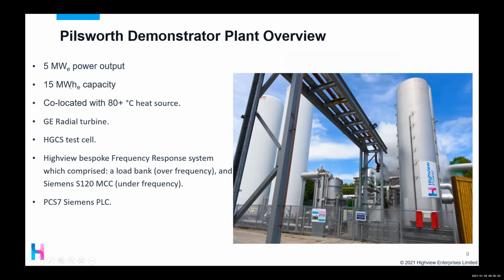It had a 15 megawatt hour electricity capacity. So at nominal power, we've got about 3 hours worth of storage. As I said before, we were co-located with approximately 80 degrees Celsius of heat. We used a GE, now Baker Hughes, radial turbine from Italy, which was a 4-stage radial turbine with 3 reheats.